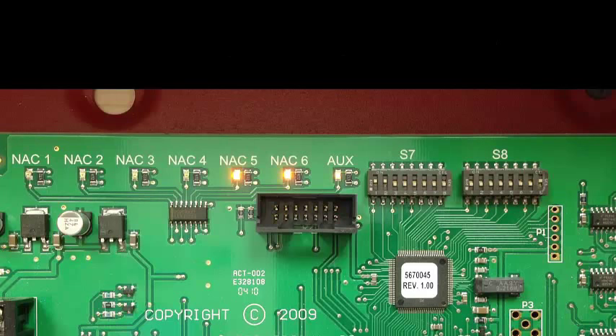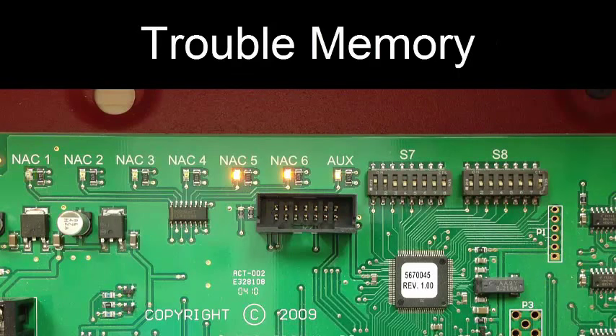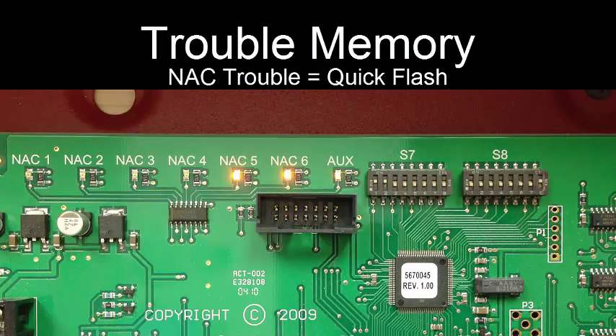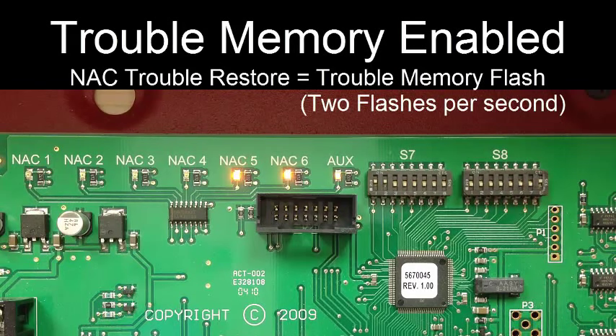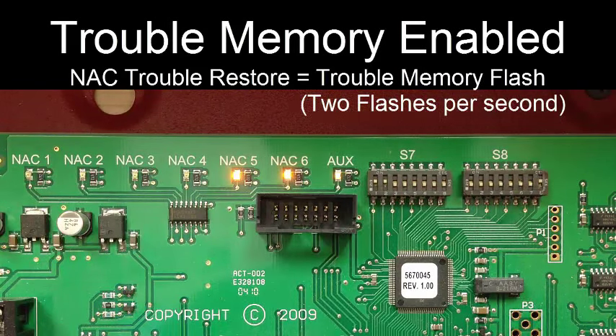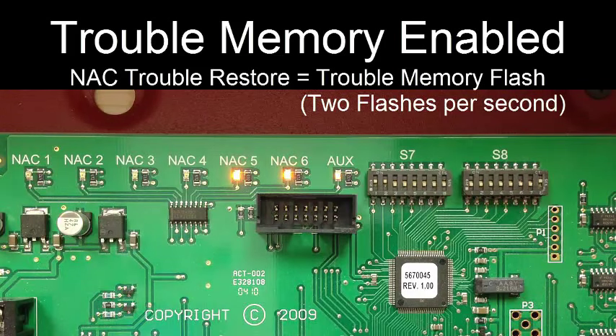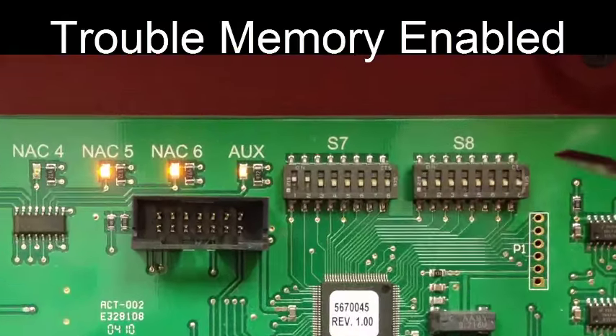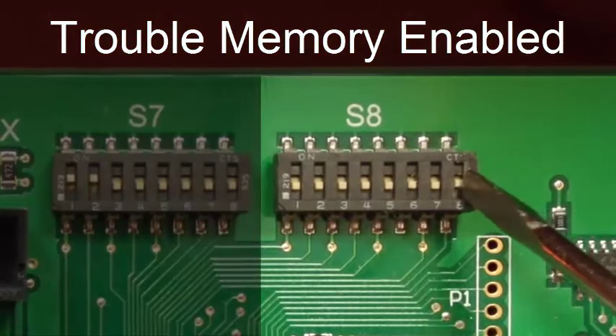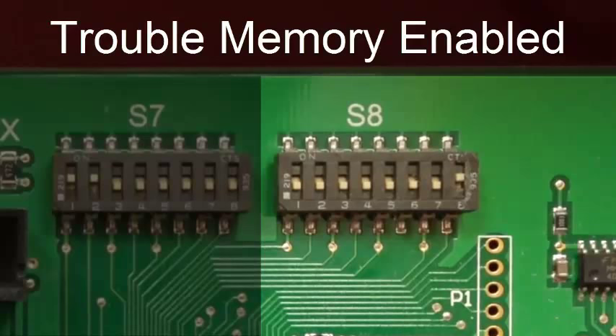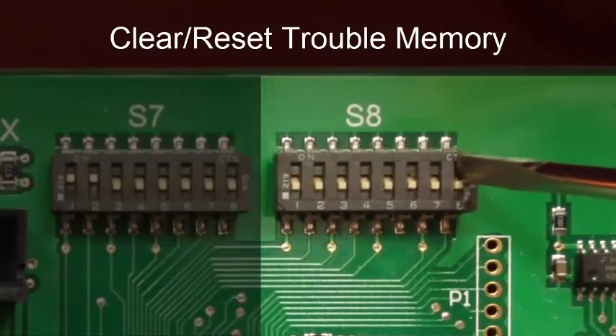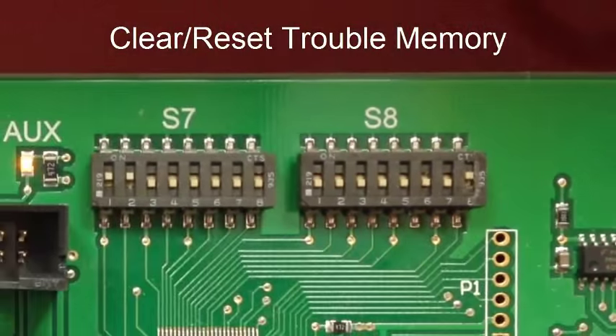Another feature of the NAC LED is trouble memory. If a NAC goes into trouble, the LED of that NAC blinks quickly. When the trouble restores, if the trouble memory feature is enabled, the LED for that NAC will begin issuing the trouble memory flash, which indicates that a trouble existed previously but is no longer present. The trouble memory indication consists of two short flashes issued once per second as seen here. To enable trouble memory, simply set DIP switch 8 of switch 8 to the on position. To clear or reset the trouble memory, set the trouble memory DIP switch to the off position, and then back on to enable the feature again.